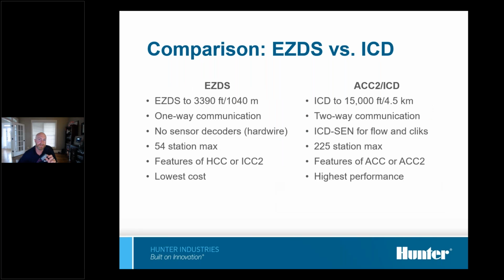So when would you use the ACC2 ICD versus the EZDS? It really depends on what the project's calling for. The EZDS, I won't say a drawback, but since it's 24-volt AC, it is bound by the physical laws of 24-volt AC power. So what that means is that the wire path distance can't be nearly as far.